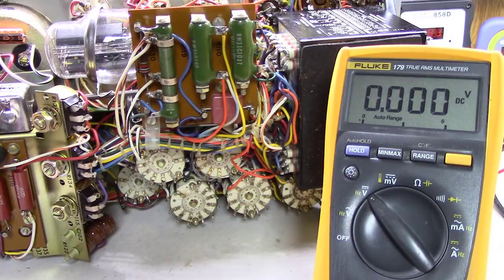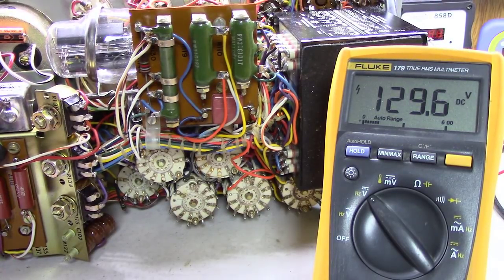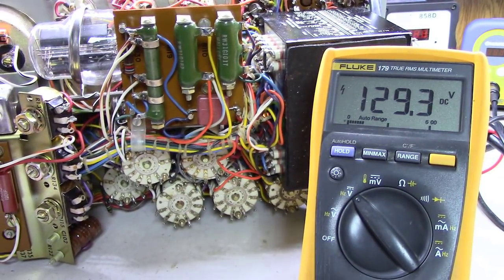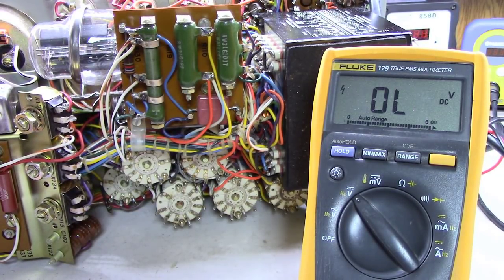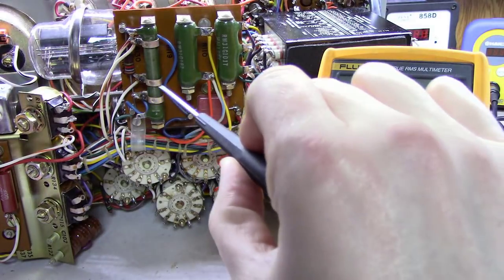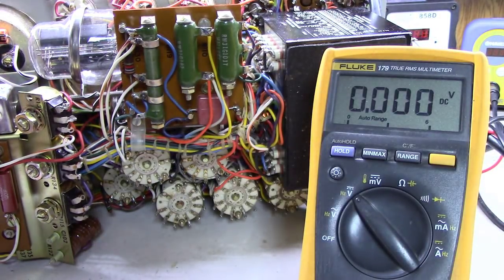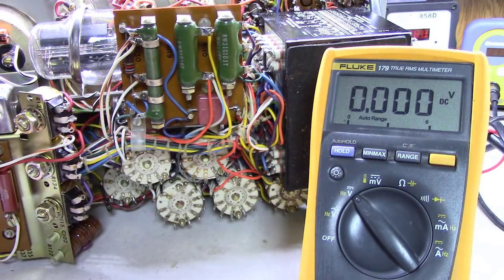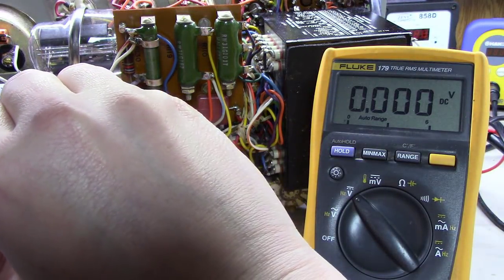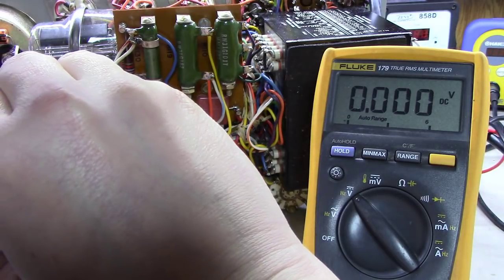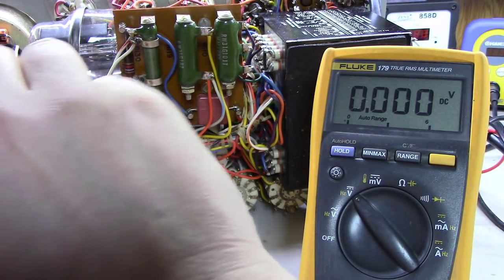Okay, as you can see now on 3 I've got 129.6. I did just a little bit more adjusting. It kept climbing up as the unit warmed up a little bit, but I'm going to leave it right in there. And then if you push buttons 2 and 3 together, 67.3, and that needs to be down at 56 volts. So I've got to adjust this middle one right here now to get to 56 volts. So I'm certainly going to unplug that unit like I just did, and I'll get my trusty little precision screwdriver out here, and I will start adjusting this thing.